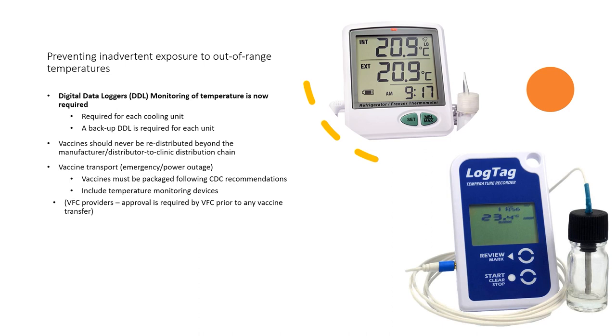A backup device should be readily available for emergency vaccine transport or when the primary data logger is sent in for calibration. In order to prevent inadvertent exposure to out-of-range temperatures, vaccines should never be redistributed beyond the manufacturer or distributor to clinic distribution chain. In the event of necessary vaccine transport, for example during an emergency or power outage, vaccines must be packaged following CDC recommendations and include temperature monitoring devices during transport. Please note that for VFC providers, approval is required prior to any vaccine transfer.